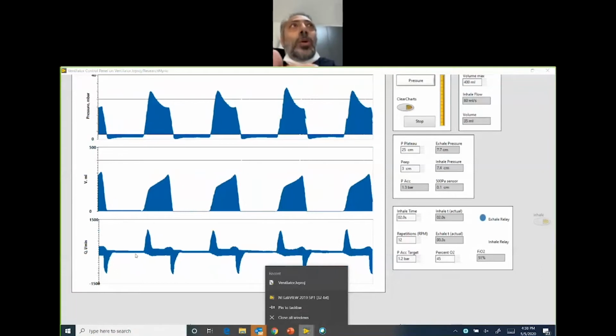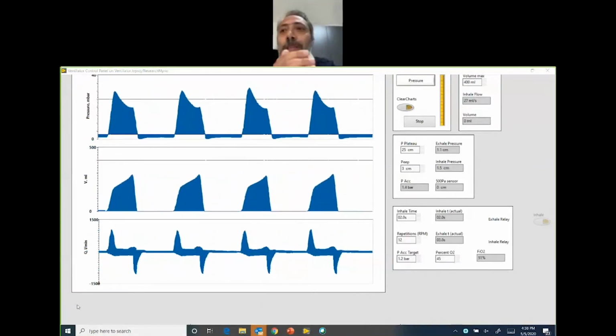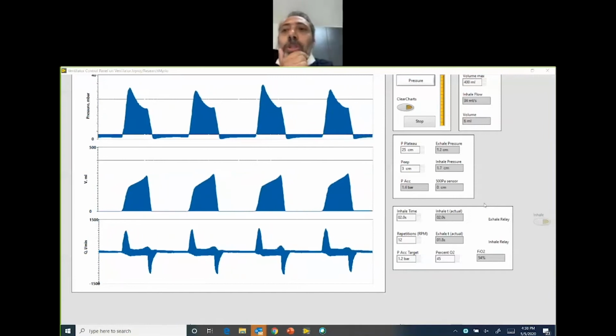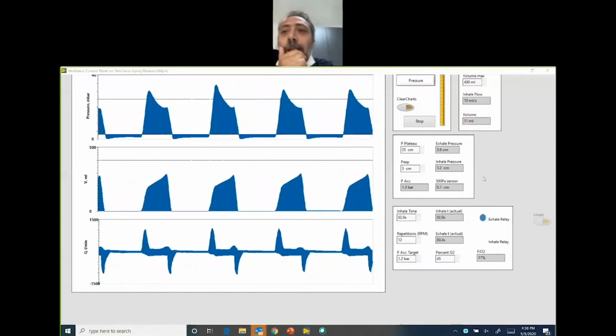With a certain ratio, we computed the pressure difference needed from the mixer to the point where we get the maximum pressure required. In other words, you deplete the accumulator, and then you say, I need 30% mixing of oxygen and air, and we start by measuring the pressure. We set a certain pressure that maps to 30% oxygen and air, and we monitor the pressure. We give oxygen at first, and then we move into air to obtain the proper mixing. This is what we have done with the accumulator, and we obtained about a 2% error, so this was highly accurate.